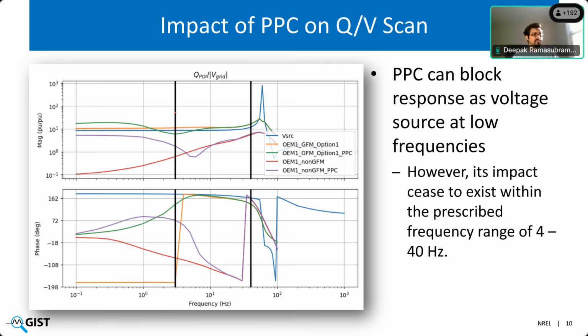If you compare the green curve with the orange curve here, the orange curve is an OEM black box model at the inverter level. The green curve is the OEM black box model with a plant controller added on top of it. Both have a supposed GFM property. You see that the phase plot of all of those curves, except for the red curve, does show a form of constant gain, because as Shahil mentioned, the non-GFM inverters can also provide a form of droop response, a form of voltage support closer to steady state. But the phase plot really shows that the value closer to 180 degrees that we're looking for in the transfer function really comes across only when you look at it at the inverter level.